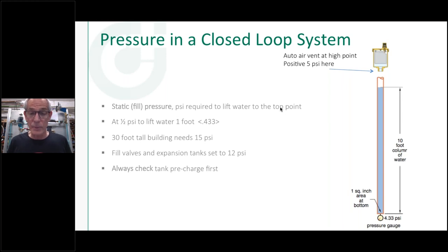One of the ways we get air out of solution and out of the system when we purge is pressure. When you walk into a mechanical room, find a gauge — if you don't trust it, take your own good test gauge: stainless steel case, glycerin-filled so it doesn't bounce to death in your truck. Turn everything off, read that gauge — that's your static fill pressure, the pressure somebody put in that system on day one. What should that pressure be? It has to do with how high you can lift water: you need 0.433 psi to lift water one foot.